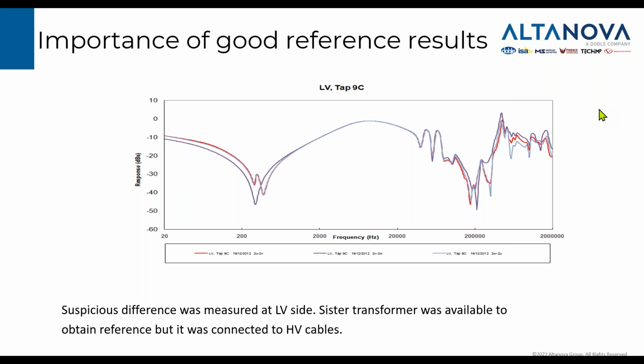And when I tested it, I noticed some differences between the traces of the low voltage side. This is not exactly the screen which is presented now. This is my second test which I did, but generally I had similar problems here. We had some disagreement between phases in this higher frequency range. So I came to the manager of the site and I said, okay, we are testing the transformer. In SFRA results, we have this problem that there are some differences. We are not 100% sure how to interpret them. Please, can you give us any reference results if you have them? They said, no, we don't have. Okay, so please, can you allow us to test the sister transformer, which is standing next to this one?